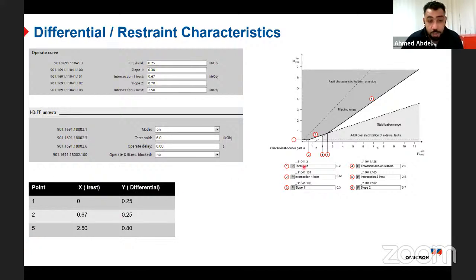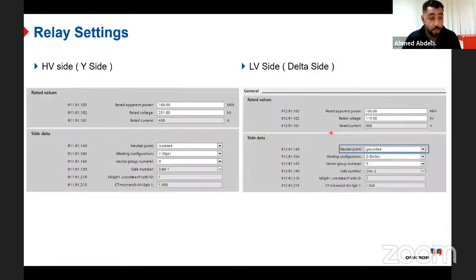Point number 5, you already know the X coordinate of it, 2.5, and you need to calculate the Y coordinate. If you define the slope of point number 1, delta Y over delta X would equal the slope, then you can get the value of the Y coordinate of point number 5. This is very simple mathematics you can do. Then you can go to our Test Universe to define this characteristic. But as I said, with the PTL, you don't need to do such a calculation.